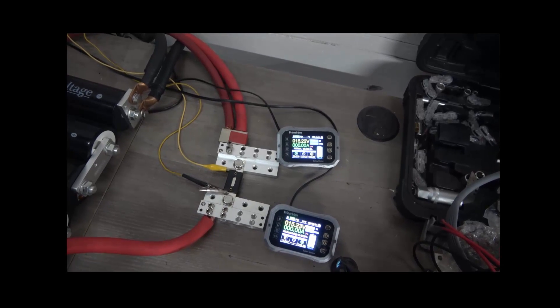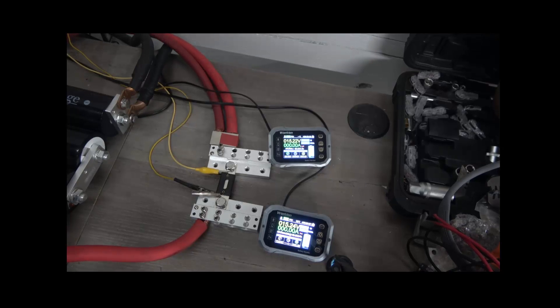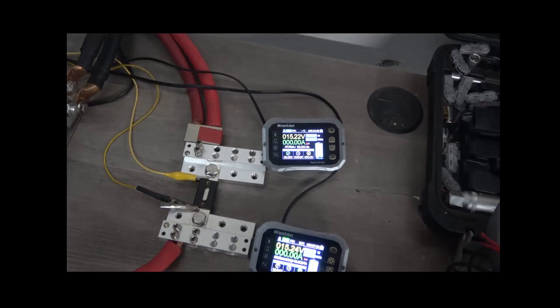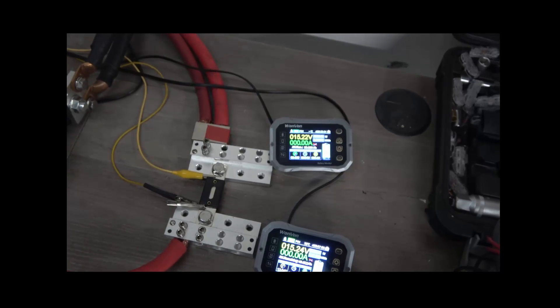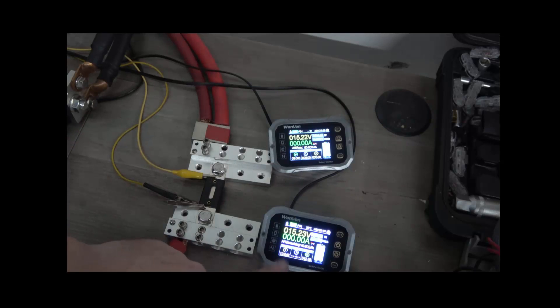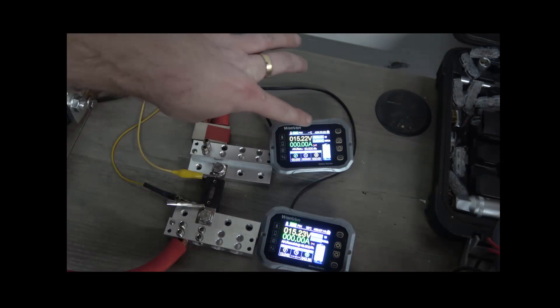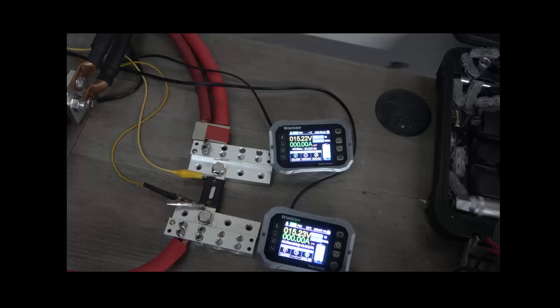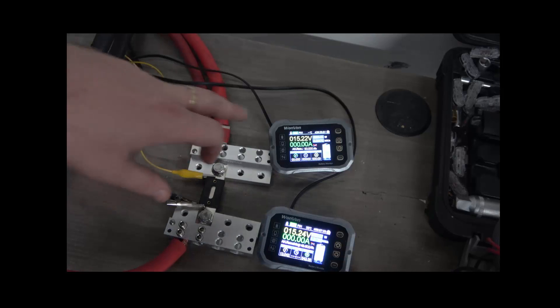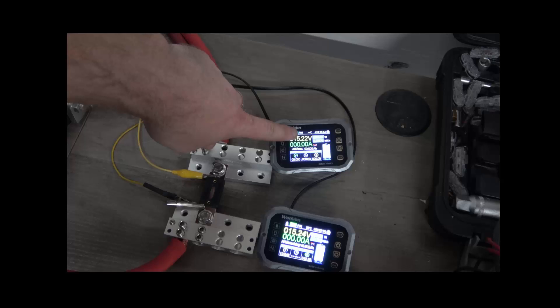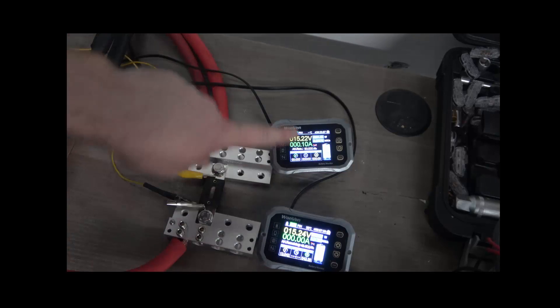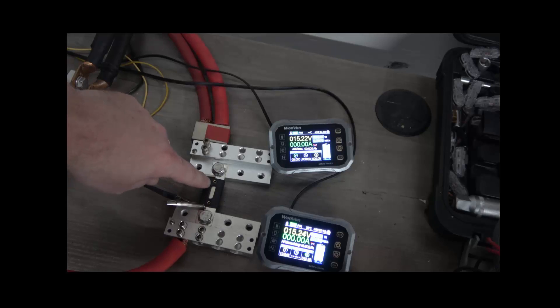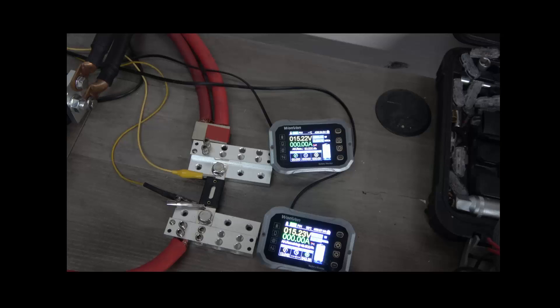Again, this is a 500 amp fuse so it should be able to handle this no problem, and then I'm going to measure the temperature and just see how it handles it. Okay, this is before the fuse and this is after the fuse. We do have like a 0.01 volt difference, 0.02, that's largely inconsequential. I'm about to turn on the current and what we're looking for is how much lower this second monitor is than this one. That's going to tell us how much power we're losing from just this 500 amp fuse if we're pulling 300 amps.